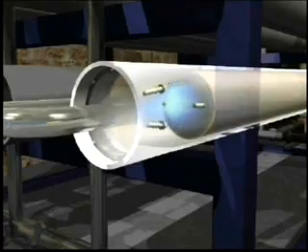Inside these vessels are the membrane elements — they are actually flat sheets that are rolled together to form a cylinder-like object. Inside these elements, pressurized water flows across the membrane; pure water passes through the membrane while the salts do not, resulting in desalinated water.